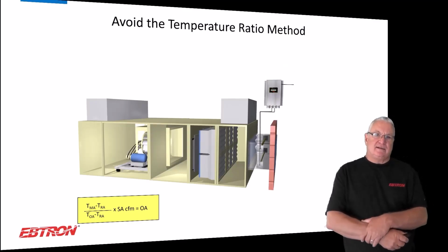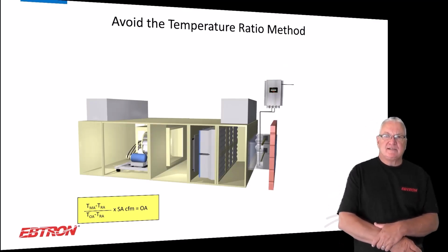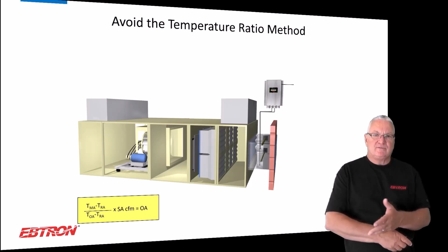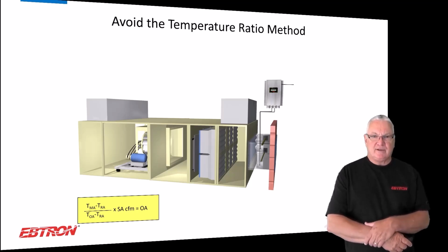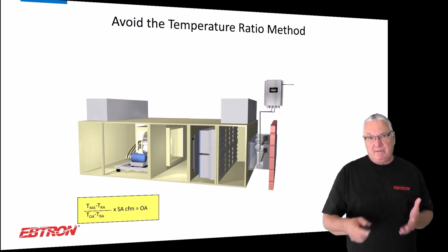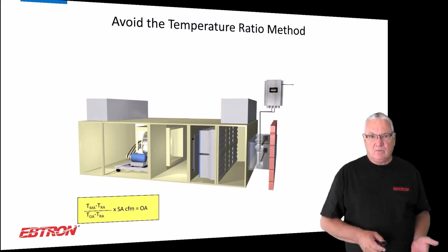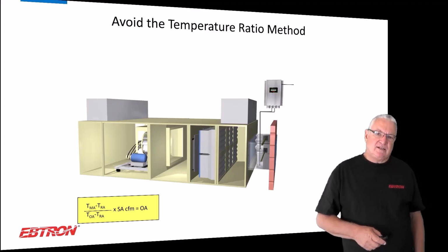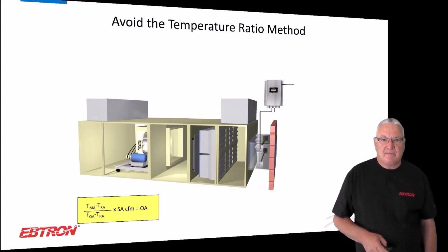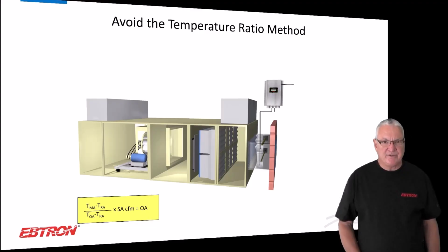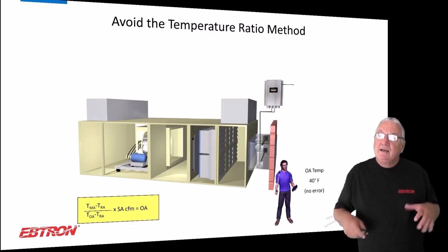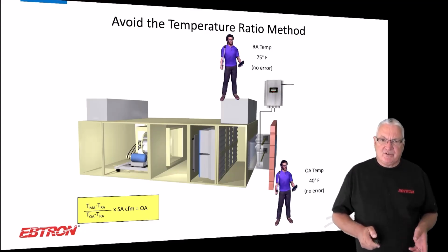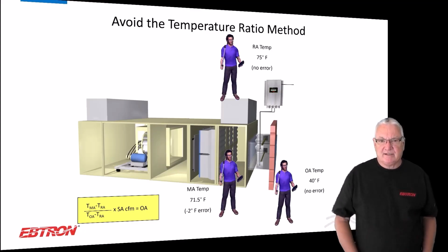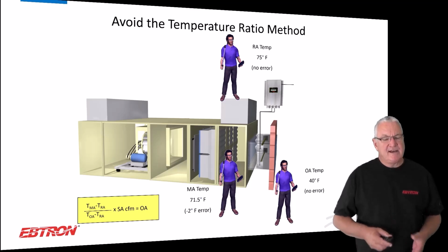Let's take a look at how we might estimate the outdoor airflow rate coming into a unit, without directly measuring it. What could we do? One thing that's been around for as long as I have is called the temperature ratio method. I called it adiabatic mixing when I was younger, and some people call it the energy balance method. It doesn't really matter. You measure the outside air temperature, the return air temperature, and the mixed air temperature. At least operationally, that's how you would do this.